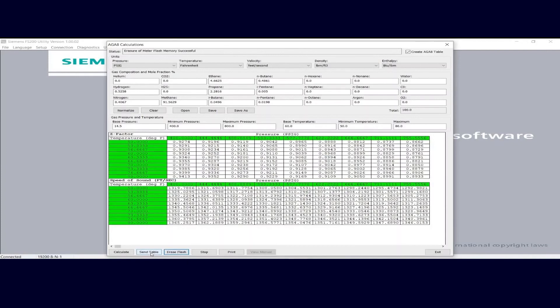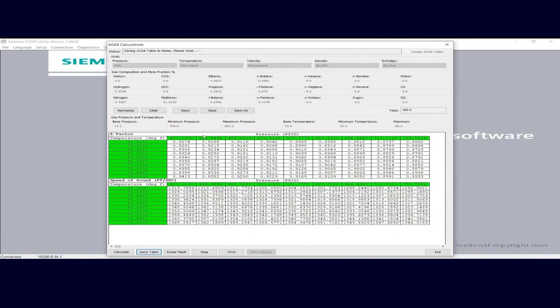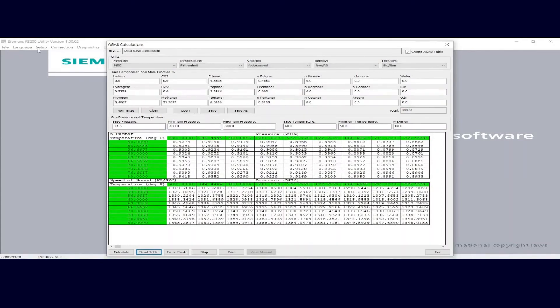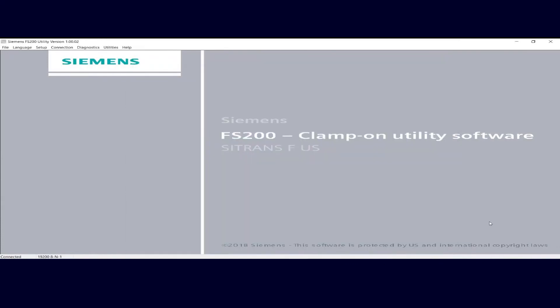Once you've done that, click the Send Table button to initiate the send to the flow meter. At the very top where it says Status, you'll see 'Saving AGA-8 table to meter, please wait.' Wait until that completes, and once it's done you can exit. You'll see 'Data Save Successful.' You've now successfully loaded your new AGA-8 table to your FS-230 flow meter. That's all there is to using the AGA-8 calculations tool in the FS-200 utility program. I hope you found this helpful — please check out all the other videos in this series covering the use of the FS-200 utility.